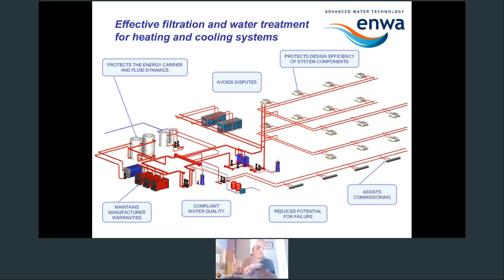So let's go on to the next slide, if I can do that. In terms of water quality considerations, there are 4 main causative factors, and these are all interlinked because water reacts chemically, physically, and biologically, and these interactions occur simultaneously. So the main 4 causes of failures are corrosion, scale, suspended solids, and bacteria, and these are all interlinked, as shown in the bottom right-hand corner of the picture.